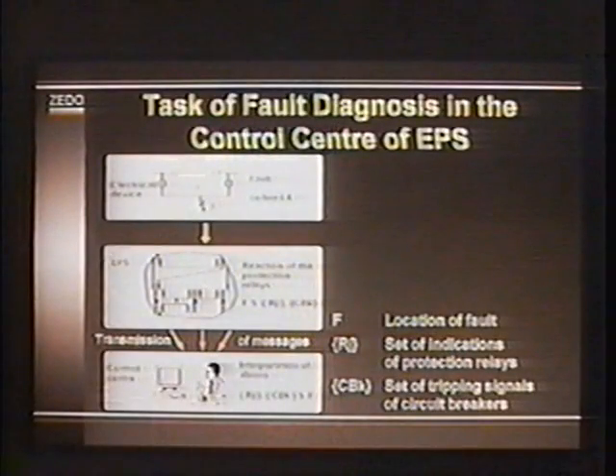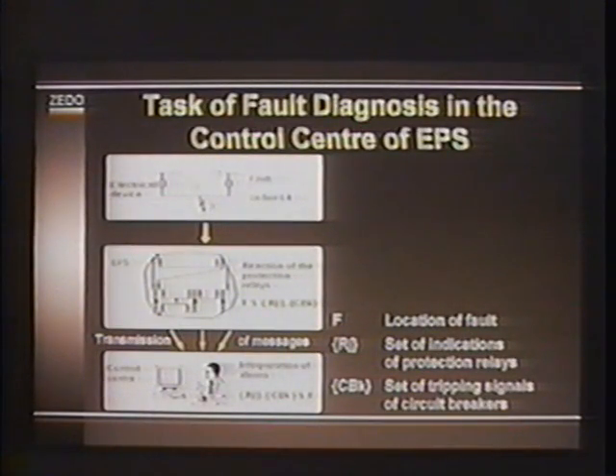The task of fault diagnosis in electrical power systems can be described by using this slide. The faults in electrical power systems can cause severe damage to components of the electrical power systems, and they can cause danger to the personnel and to other people who are working next to the faulty element. Therefore, lots of protection devices are installed in the electrical power systems. For example, lines are protected by protection relays, which are installed at the end and at the beginning of the lines. And it's the task of these protection relays to detect electrical faults and to switch them off selectively and as fast as possible.